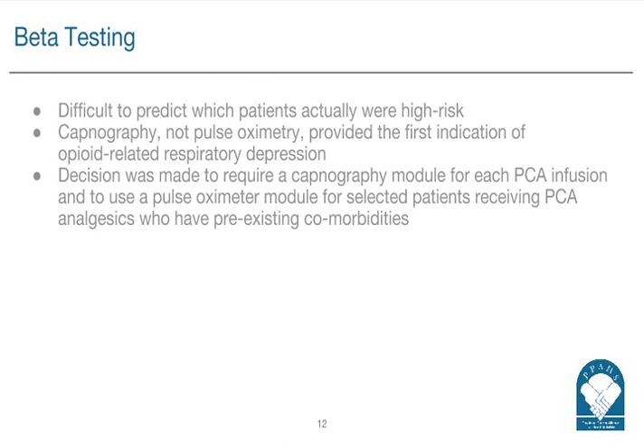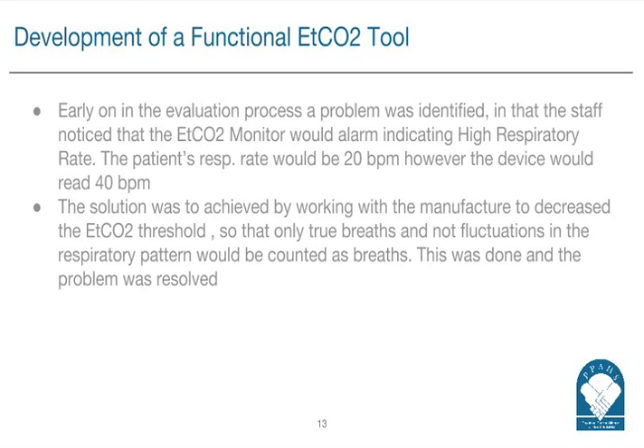Did you have to go through changes to make this new system work? We went through a lot of changes initially — this was about 10 years ago, and we were the first to put this out on the floors in the general care area for all our PCA patients. Capnography works really well in the ICU with intubated patients and in the OR, but now we were talking about patients on the floors with a variety of ventilatory statuses. Patients would come back from the OR pretty well sedated, then wake up and want to walk, talk, and eat. We saw that the algorithms had to be adjusted because we were having alarms and readings that weren't accurate.